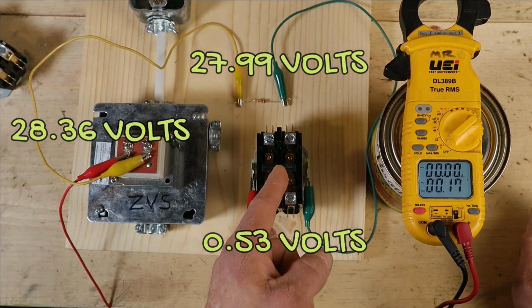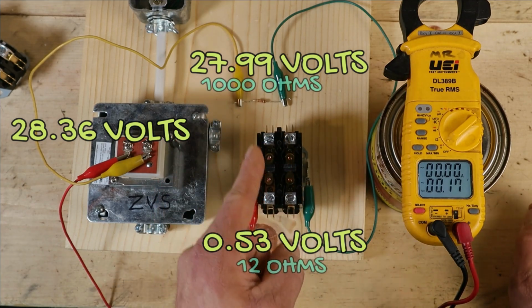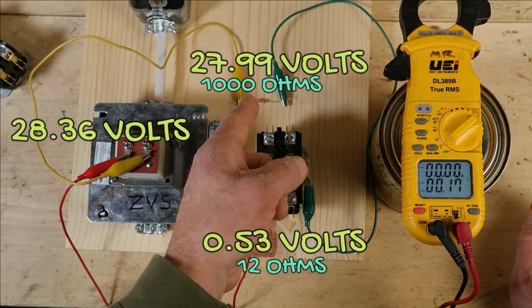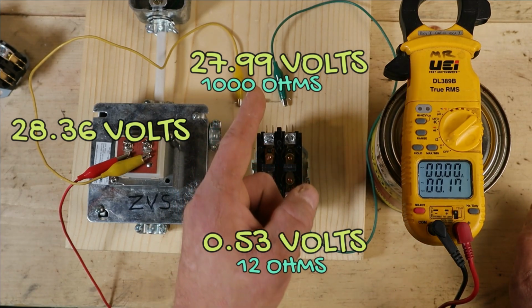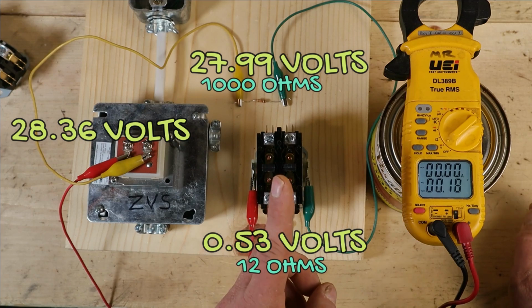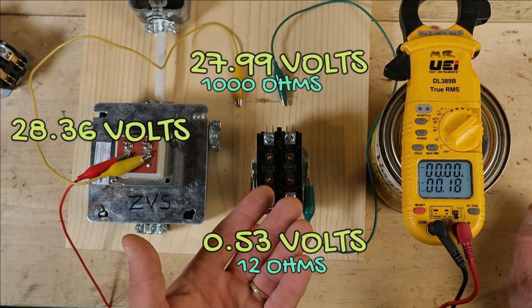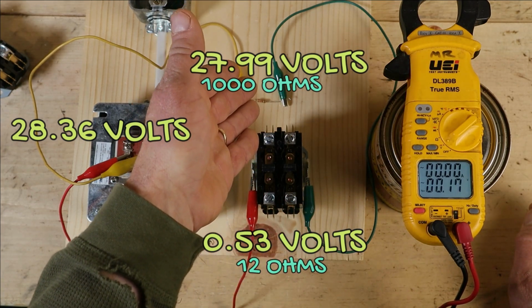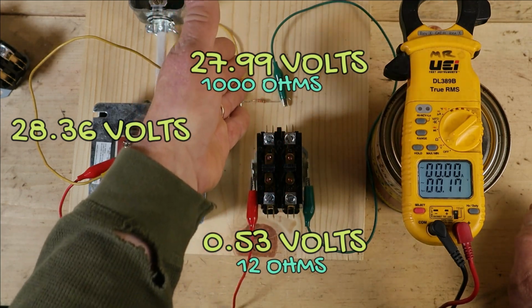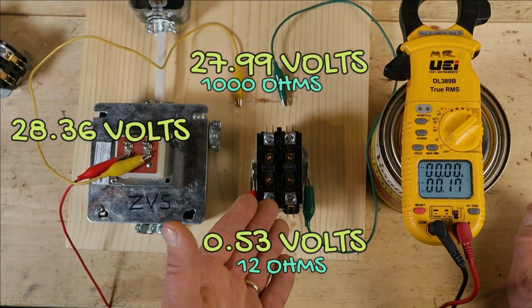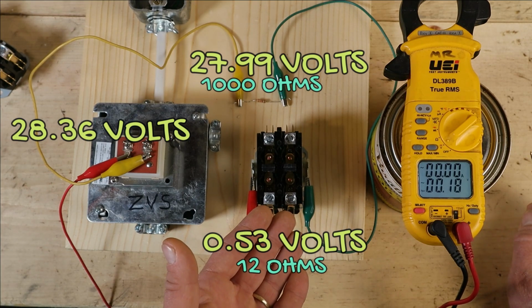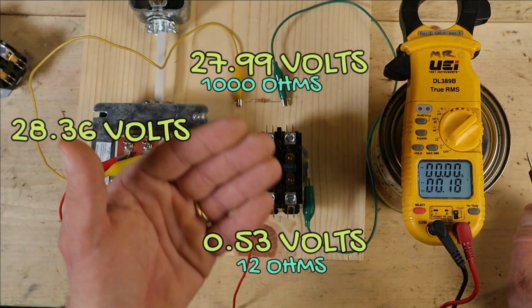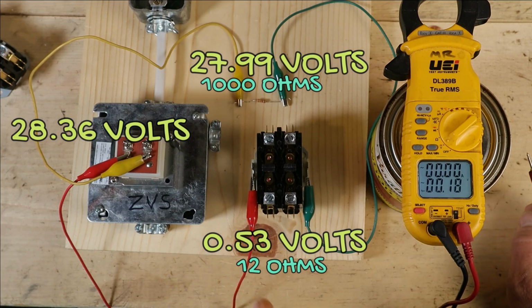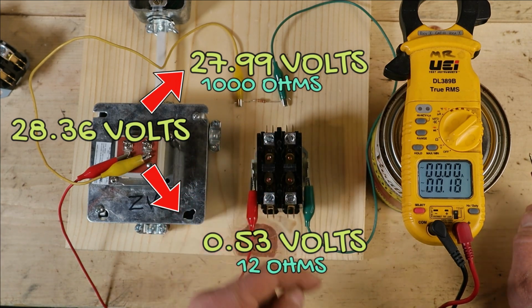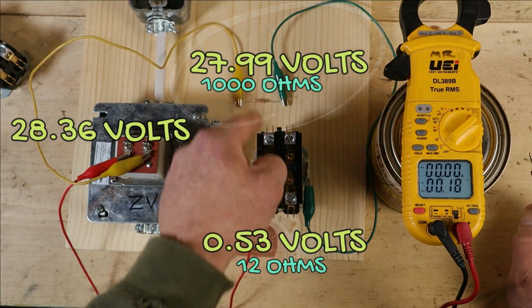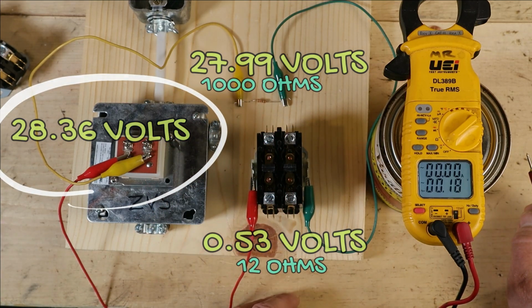Why is the contactor not pulling in? What we have here are 2 points of resistance in this circuit. Now that resistor is definitely the highest point of resistance, and what we're seeing here is the relationship that voltage has with different points of resistance in a circuit. So with the higher resistance, all the voltage is going to that point, and the component with the lower resistance is barely getting any voltage at all. So what's happening is that these two different points of resistance are causing our voltage to split. And the point of higher resistance is getting most of it. But when we add the two together, we're getting the full output of the transformer.